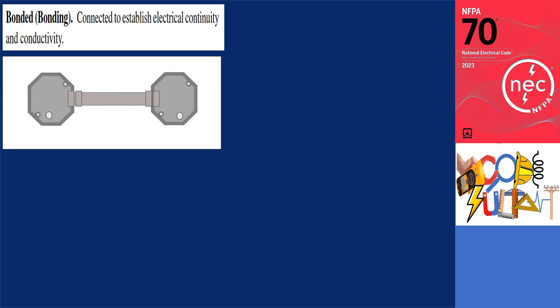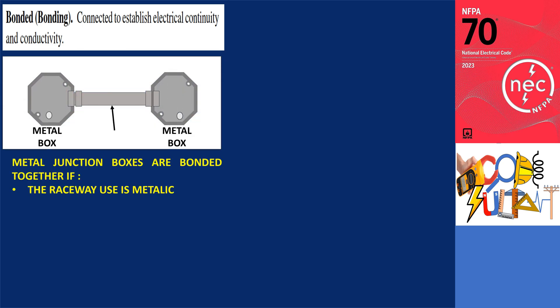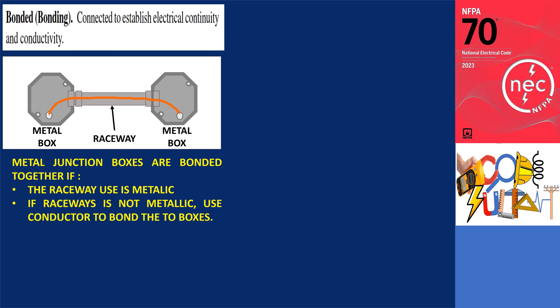Let's begin with the definition of bonded according to the Codesultant. Bonding refers to the connection made to establish electrical continuity and conductivity. In our first illustration, if the raceway used is made of metal, the two metal boxes are automatically bonded. However, if non-metallic raceways are used, a conductor or jumper is required to bond these two metal boxes together. This ensures electrical continuity between them.